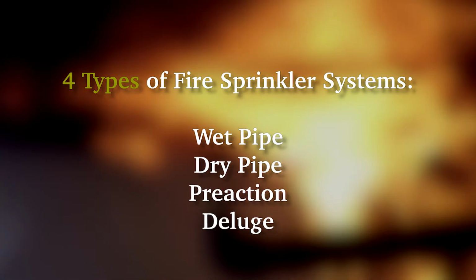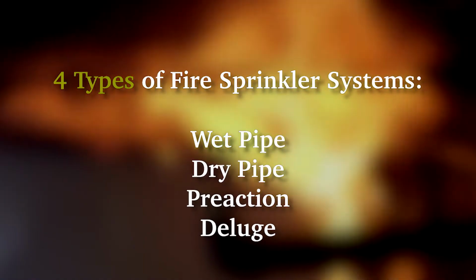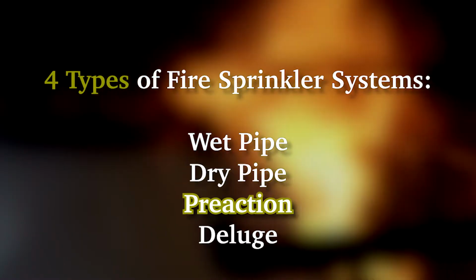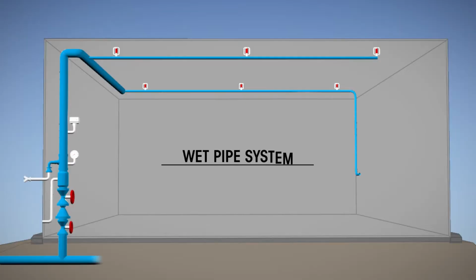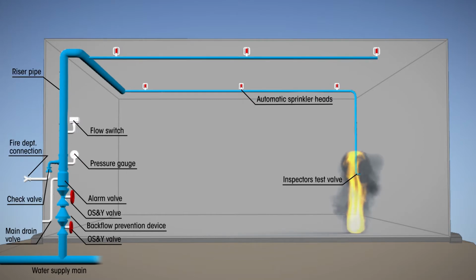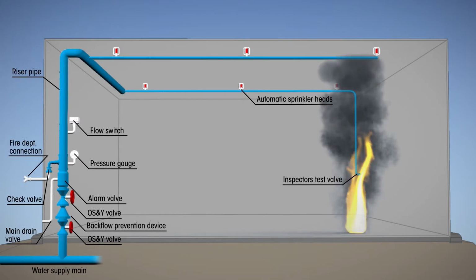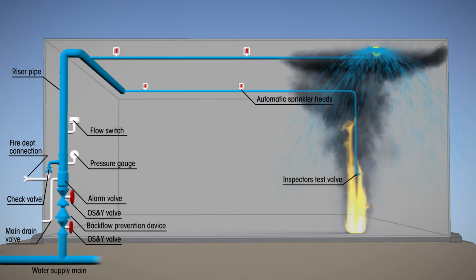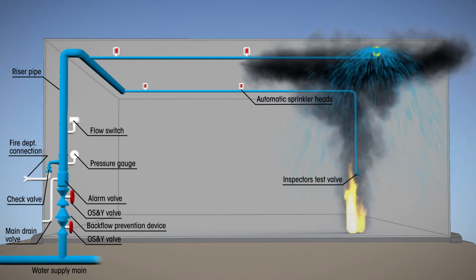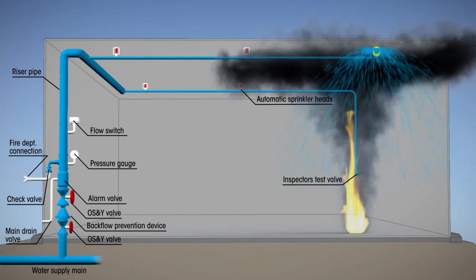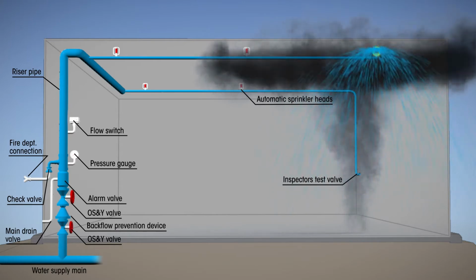There are 4 major types of fire sprinkler systems: wet pipe, dry pipe, pre-action, and deluge. Most people are familiar with wet pipe fire sprinkler systems, in which automatic sprinklers are part of a piping system containing water that is connected to a water supply. The heat from a fire individually activates the fuse or bulb in a fire sprinkler, which causes water to flow immediately.